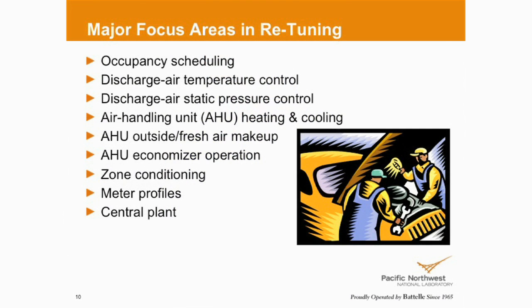How are our economizers and our ventilation systems? Are we over-ventilating or under-ventilating? Do we have demand control ventilation? How are our economizers - are we bringing in outdoor air when it's proper and economical to do so, to reduce or eliminate our mechanical cooling loads? What's going on in our zones? Are terminal boxes separate? Do we have perimeter hot water? Are they sequenced with each other?